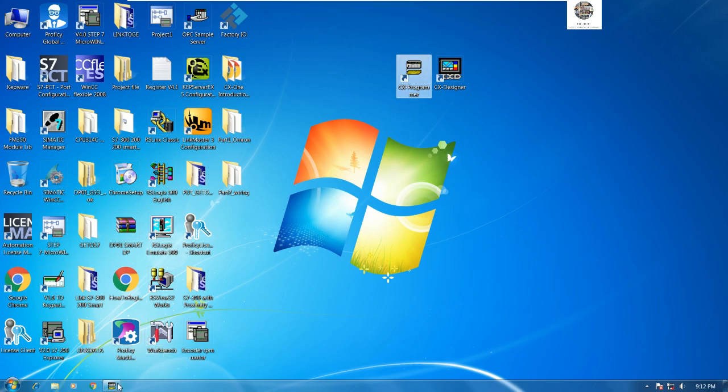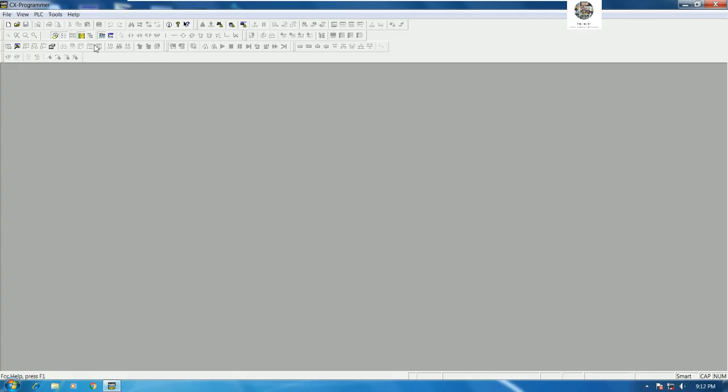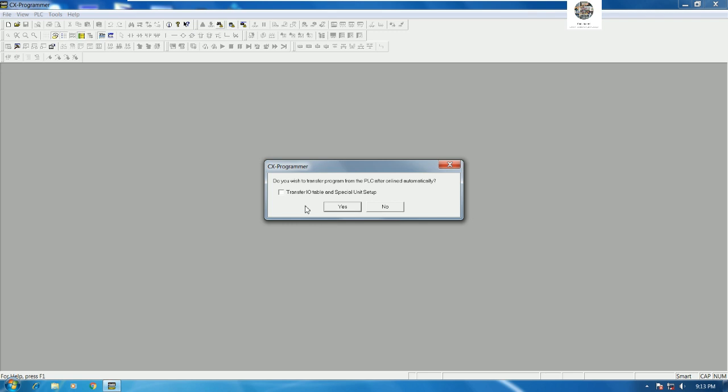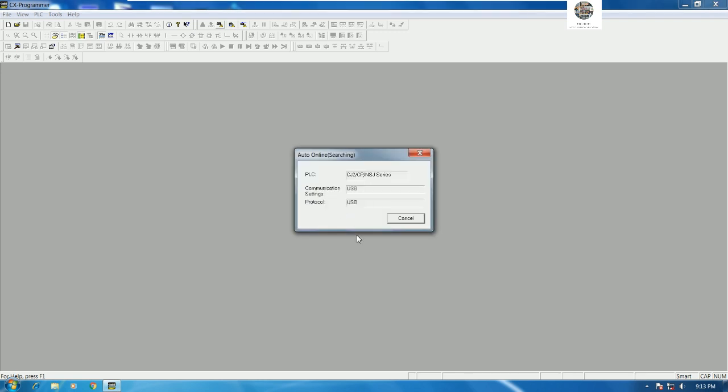Let's go to our software. Right now we already opened the CX Programmer software. The first step we can go direct online, and then choose USB. Choose here USB and then click Connect. It will upload the data or program from PLC by searching the PLC connection automatically. Let's click Connect and then choose Transfer IO table and special unit setup and click Yes. Wait a moment for searching automatic online and searching the PLC device that's connected with our computer.